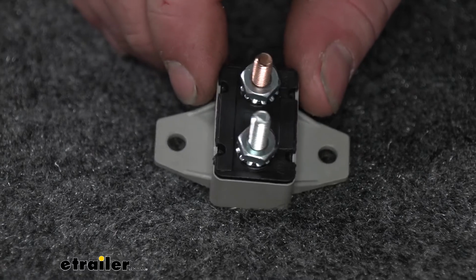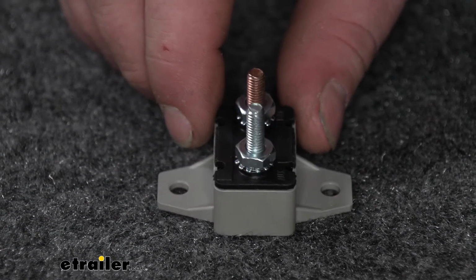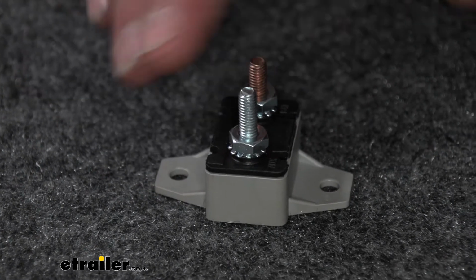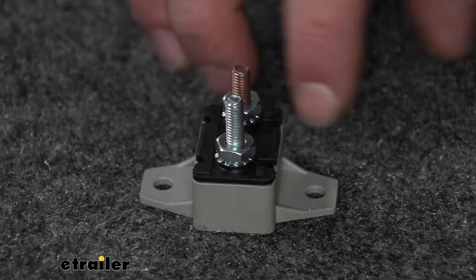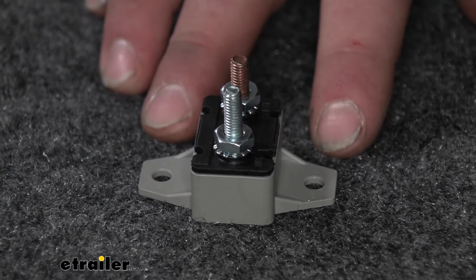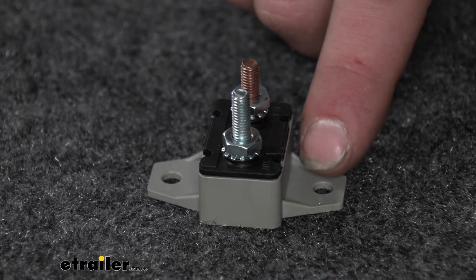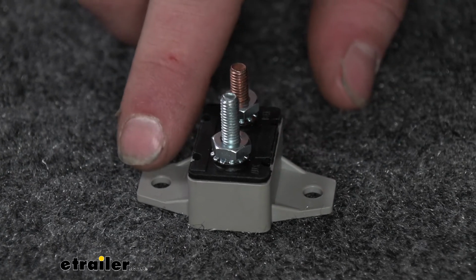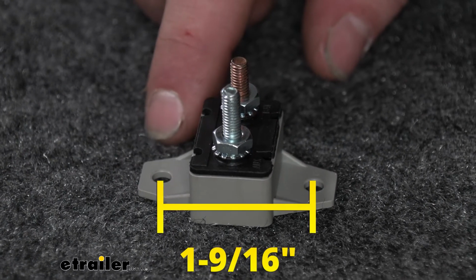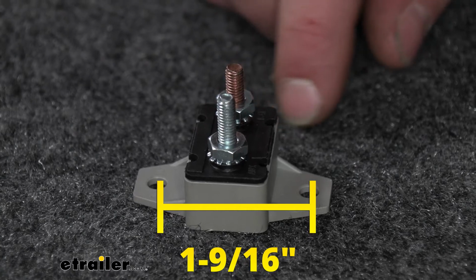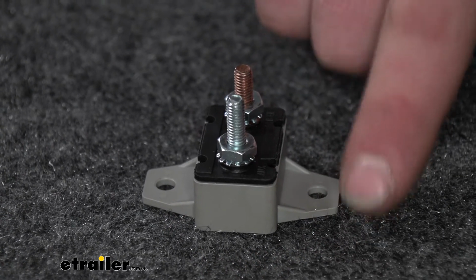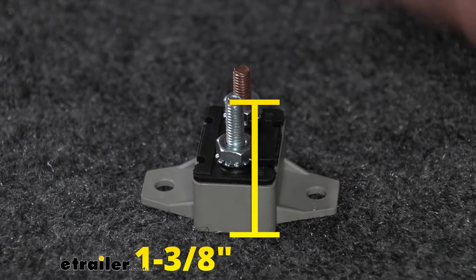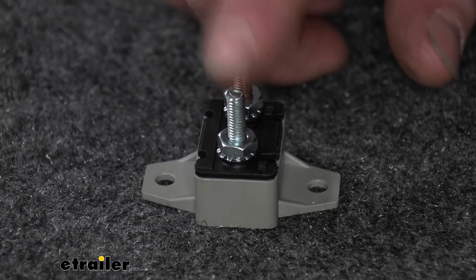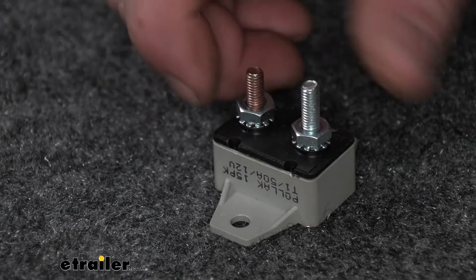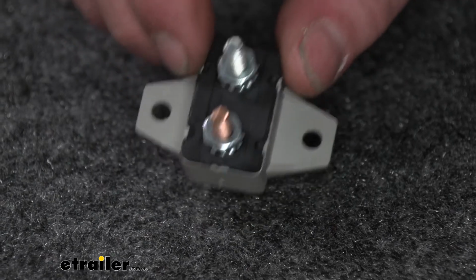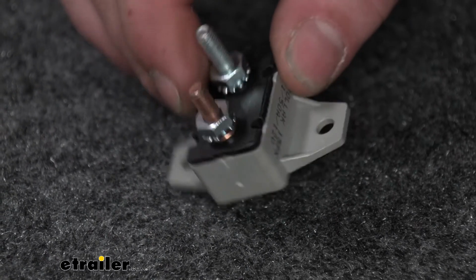I understand these breakers can be mounted in relatively tight spaces, so a couple of quick measurements might help. From the center of one hole to the center of the other hole, it's about 1 inch and 9/16. From the bottom of the breaker to the top of the post, it's about 1 inch and 3/8. So relatively compact, and unless you're in an extremely tight spot, you should be able to mount this just about anywhere.